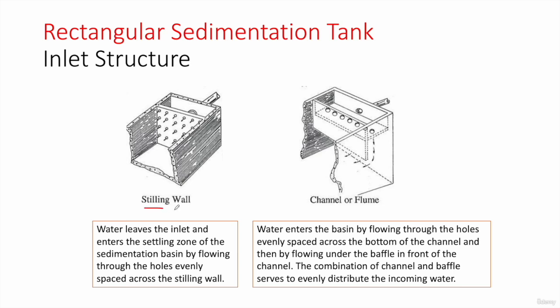This is a 3D view of an inlet structure — a stilling wall or baffled wall, which is the most commonly used inlet structure. Water comes in through an inlet pipe, enters the inlet chamber, and leaves evenly through the holes across all parts of the sedimentation tank. We can also use a channel or flume, where water enters through an inlet pipe into a perforated channel and then leaves under the baffled wall into the tank.